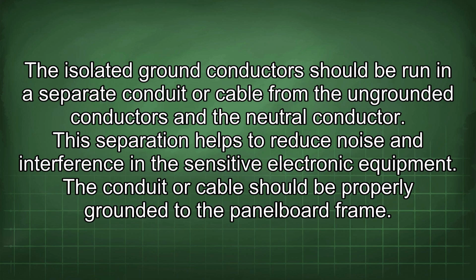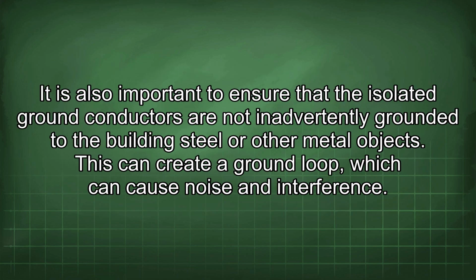The conduit or cable should be properly grounded to the panel board frame. It is also important to ensure that the isolated ground conductors are not inadvertently grounded to the building steel or other metal objects. This can create a ground loop, which can cause noise and interference.